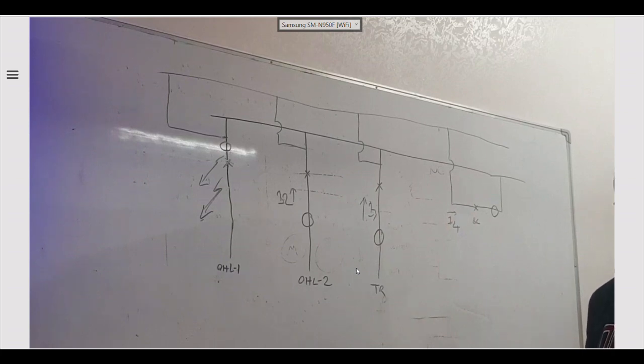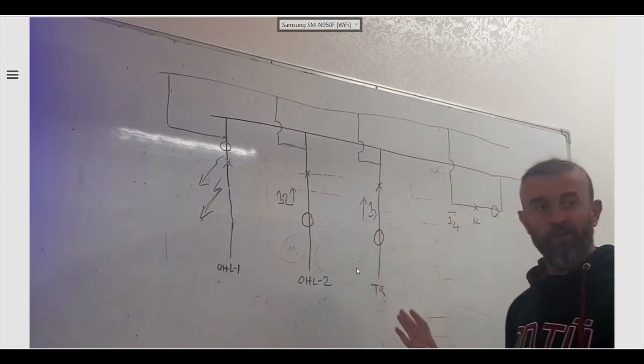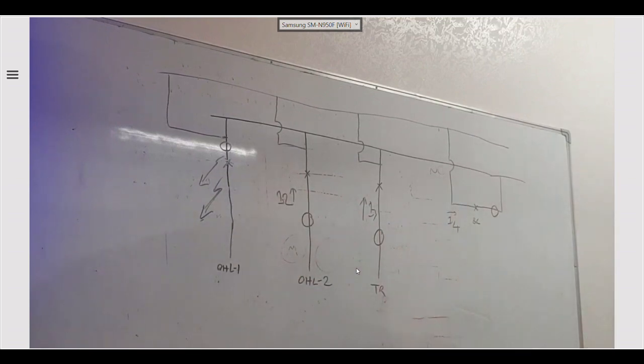That means the end fault protection works according to the status of the circuit breaker, right? Yes, yes. It is enabled when the circuit breaker is open, and when it is closed, it is disabled automatically. Okay. So with those two cases, is it okay about the logic? Okay. As a third case, for the bus coupler case.